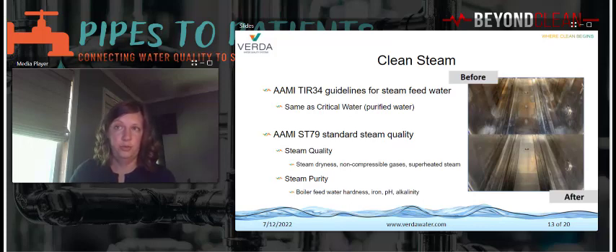Corrosive dissolved salts are removed from the steam feed water. Fewer boiler blowdowns and sterilizer chamber cleanings are required. Staining and spotting agents are eliminated. No residues are deposited by the steam onto medical instruments, eliminating potential sites for future microbiological growth once the instrument surfaces have cooled down. Dry steam ensures there are no wet packs at the end of the sterilization cycle. Microbial and pyrogen-free feed water results in microbial and pyrogen-free steam.